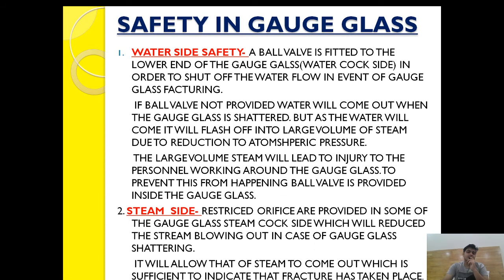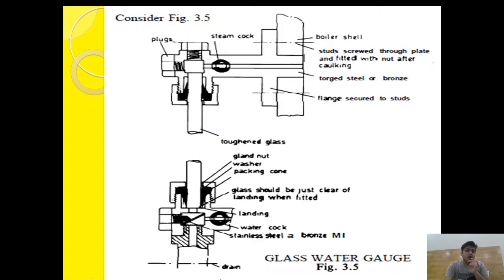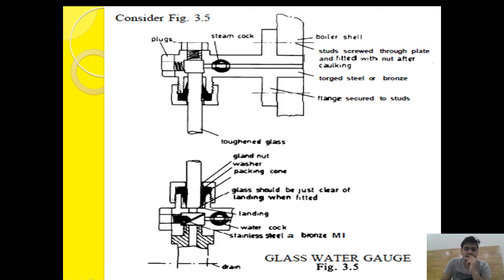Now let's see the steam side safety. A restricted orifice is provided on some gauge glass steam cock sides, which will reduce steam blowing out in case of gauge glass shattering. It allows only enough steam to come out that is sufficient to indicate a fracture has taken place, but restricts the forceful gushing of steam that could affect personnel working around the gauge glass.